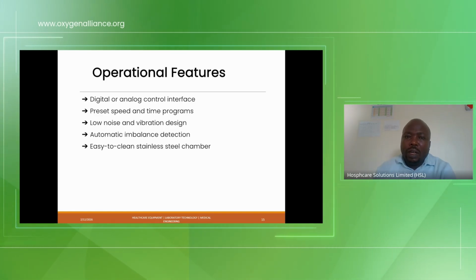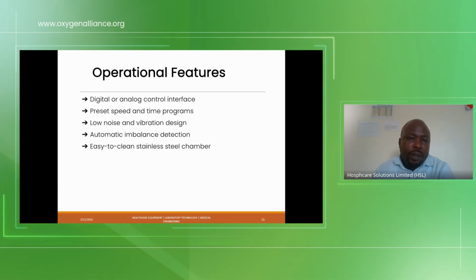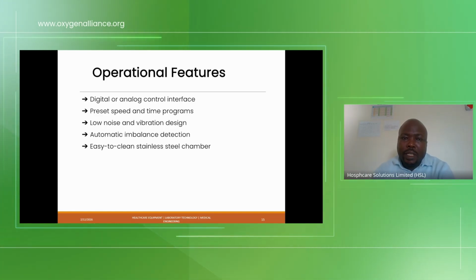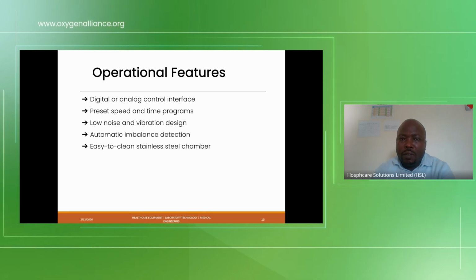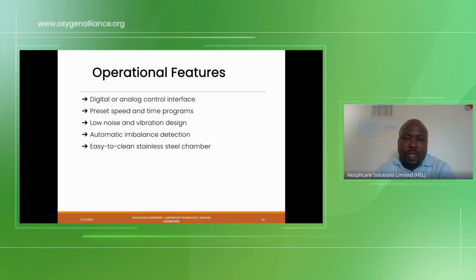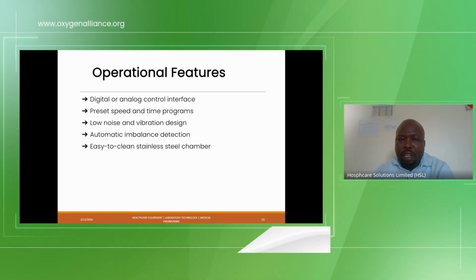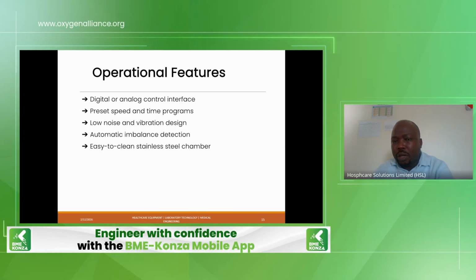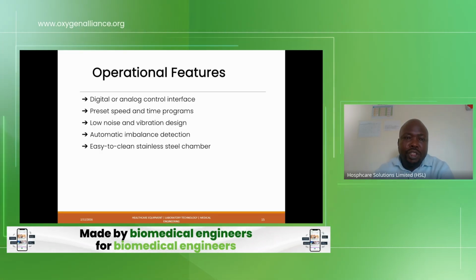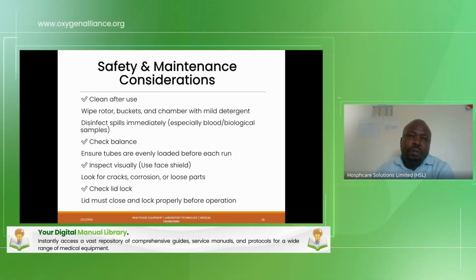We have a digital or analog control interface, a user interface. We have preset speed and time programs, low noise and vibration design, automatic imbalance detection, and an easy to clean stainless steel chamber in case of any spillage. Now, this is the area of interest for most of you. We have safety and maintenance considerations.